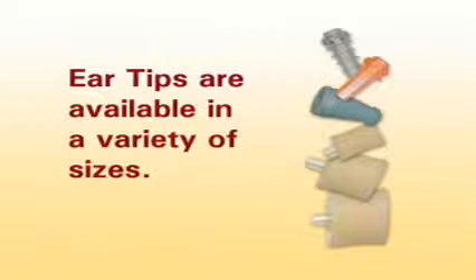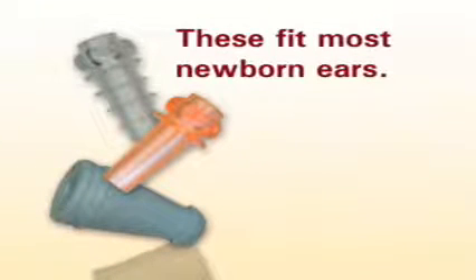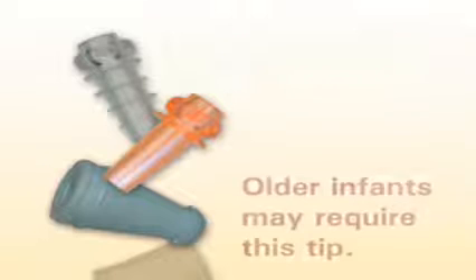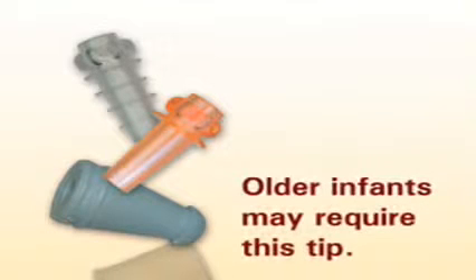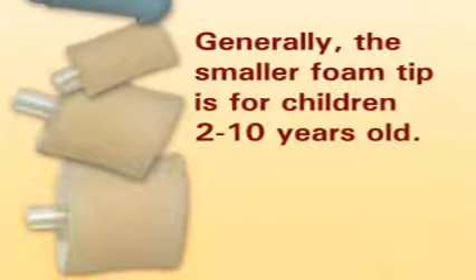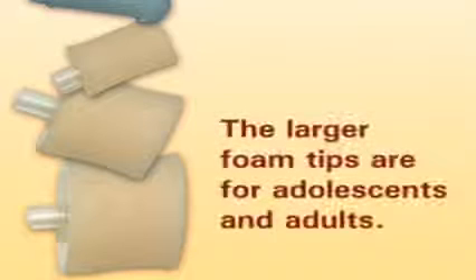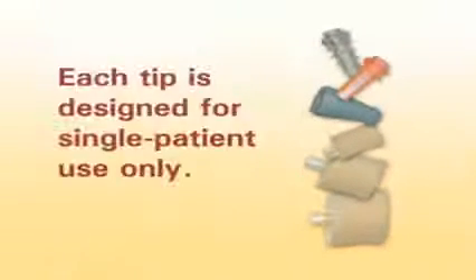The ear tips are available in a variety of sizes. Generally, the clear flanged ear tips or the pink-tinged preemie tips fit most newborn ears, while older infants may require larger tips. The smaller, beige foam tips fit most children between 2 and 10 years of age, although some adults with small ear canals may require this tip size as well. The larger foam tips are for adolescents and adults. Each tip is designed for single patient use only and must be discarded after the test.